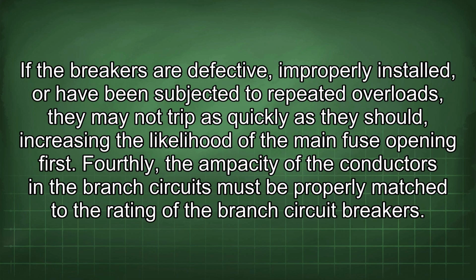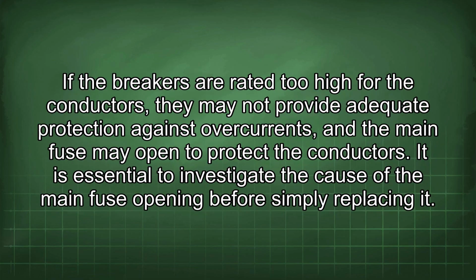If the breakers are defective, improperly installed, or have been subjected to repeated overloads, they may not trip as quickly as they should, increasing the likelihood of the main fuse opening first. Fourthly, the ampacity of the conductors in the branch circuits must be properly matched to the rating of the branch circuit breakers. If the breakers are rated too high for the conductors, they may not provide adequate protection against overcurrents, and the main fuse may open to protect the conductors.